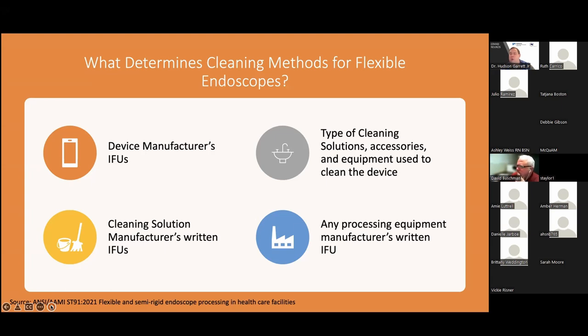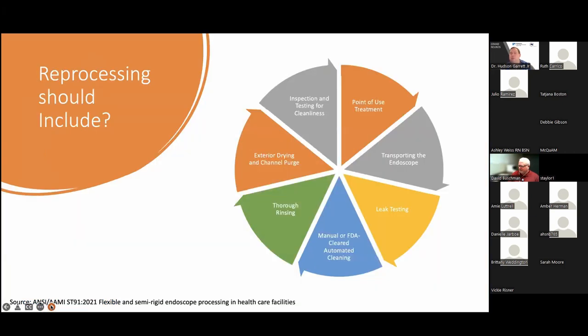There's also the overall steps for cleaning and disinfection, and how we store the equipment. For example, if you walk into a GI suite and see diapers at the bottom of a storage cabinet with dripping water coming down from the hose, that automatically tells you there's an issue, because those devices shouldn't be draining onto a diaper, onto a floor, into a cabinet, creating humidity that's going to create organisms. That's a perfect setup for a fungal pathogen. So we want to ensure we're following the instructions for use, but also setting up our environment to win, reducing the risk for cross-contamination.